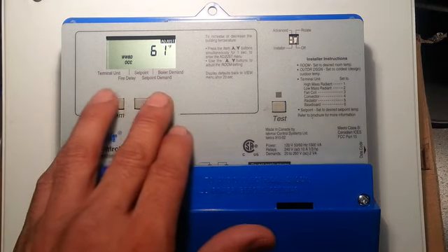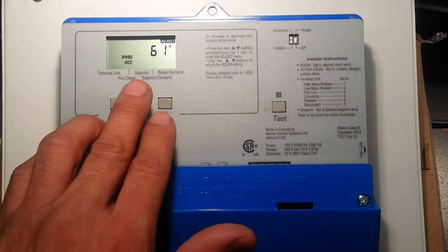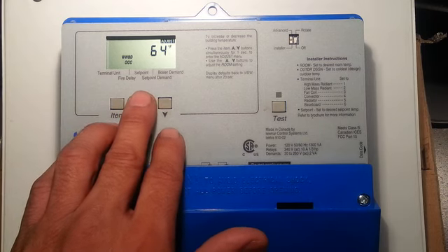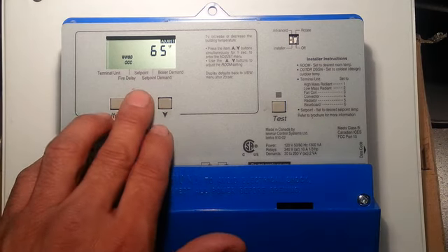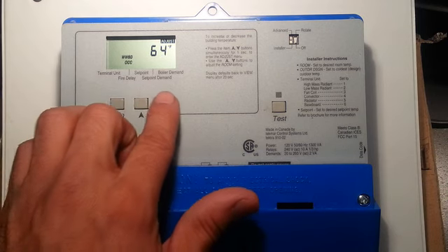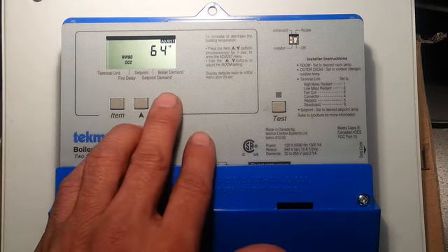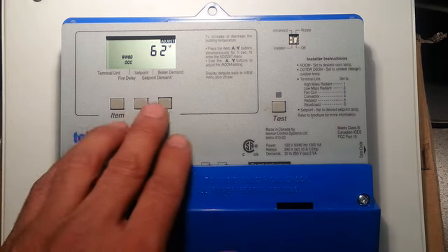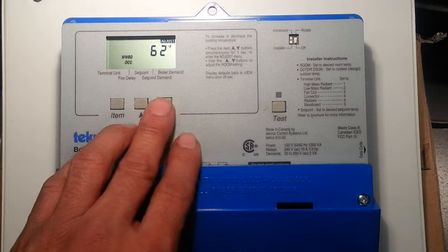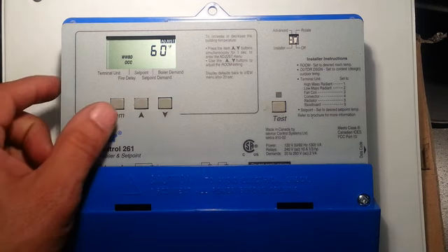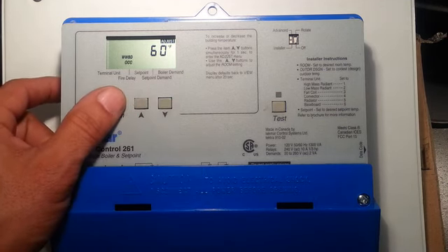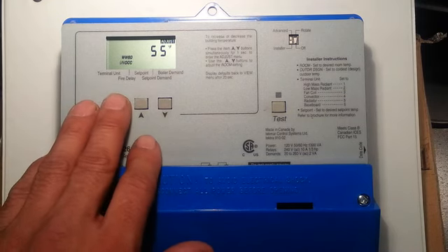But if it's in an older folks home, and the people there usually like their heat until it's 65 or 70 degrees outside, you're going to have to move this number up. Otherwise you're going to get a nuisance call when there's no sun shining and no solar heat going into the building. That building will typically be fairly cool, and you'll get a call that they're too cold or the boiler's not working, when it's actually just in warm weather shutdown mode. Warm weather shutdown in the unoccupied mode is the same thing, but it's not used typically in commercial.